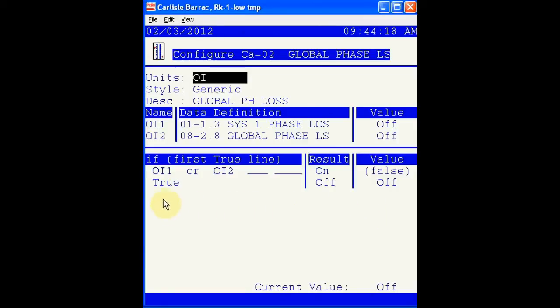In this case, the calculation is programmed so that on-off input 1 or on-off input 2 becoming on will result in a current value switching to on. The true line is used to tell the calculation what to do if neither input is on. In this case, the calculation will be off. Another way of looking at the word true is to think of it as the word else, which is used in many PLC programming strategies.